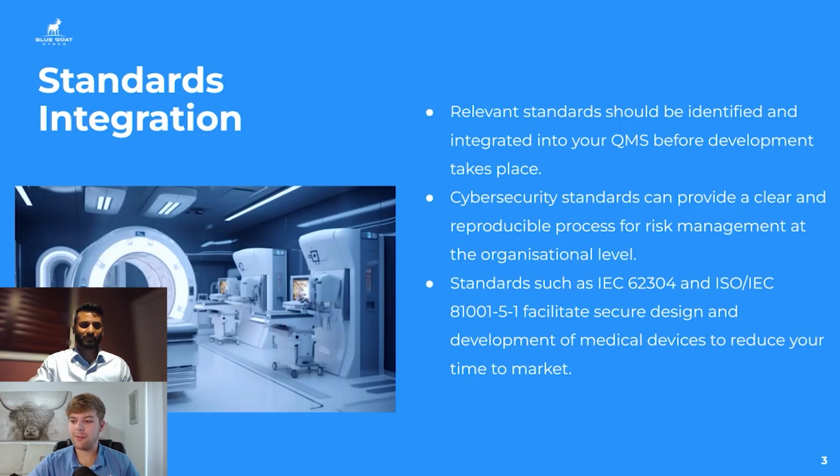And I think another big part of this as well is a lot of clients will submit the FDA required documentation, which are typically going to be the artifacts of all of these processes, but not the processes themselves. If you have the artifacts, it should act as evidence that you have these standards integrated. But if you aren't doing it properly, the time may come where there's an FDA audit or they're trying to collect any of your metrics. This is especially going to be important for a PMA submission where you have these PMA annual reports. When that time comes, if you are just preparing the documentation to have a final result as opposed to looking at the process, it's going to be very difficult to reproduce those.